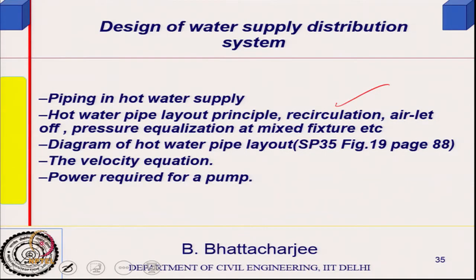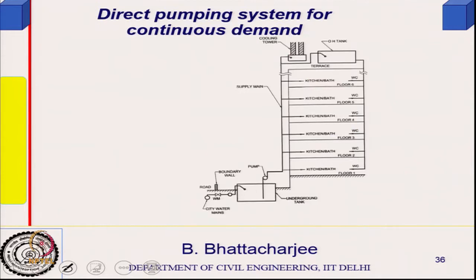Recirculation is the main consideration for hot water pipes. Hot water pipe layout principles: recirculation, air let-off because vapors would generate and create pressure. Therefore, there has to be venting and air let-off, and pressure equalization at mixed fixtures where you are mixing hot and cold — pressure equalization should be there. SP 35 figure 19 on page 88 gives you a hot water supply system diagram and some idea related to power.